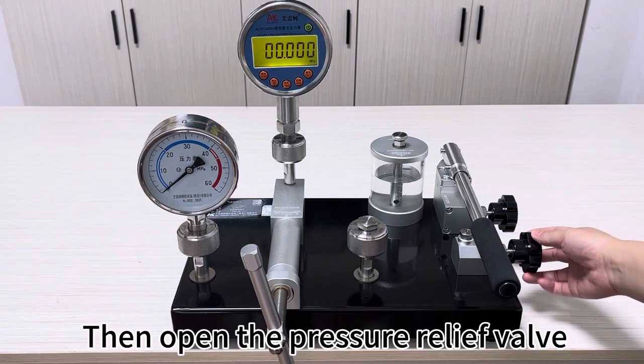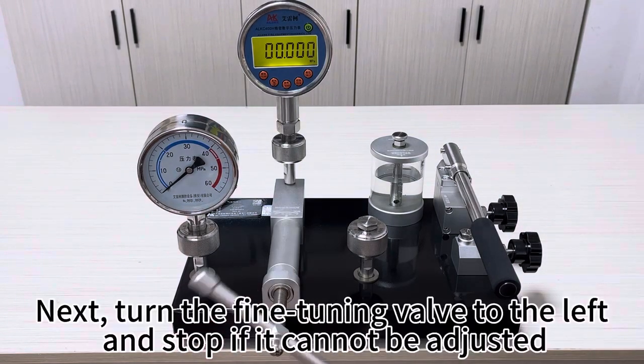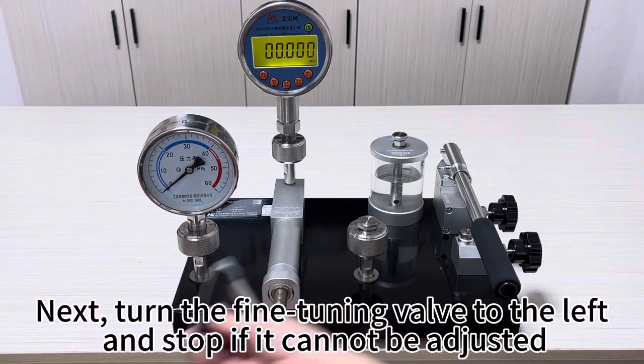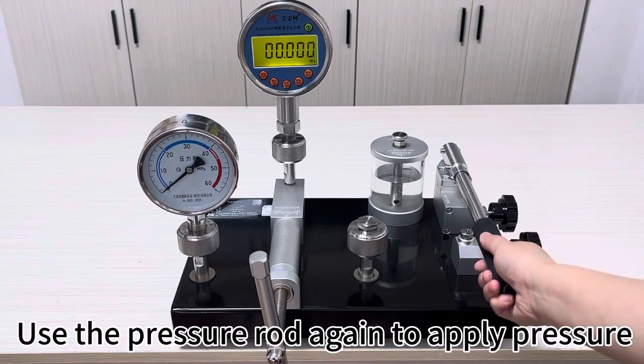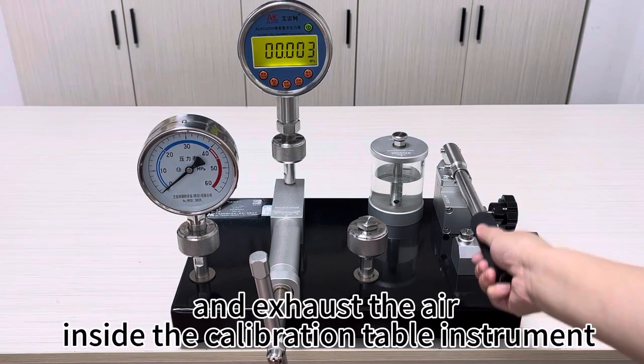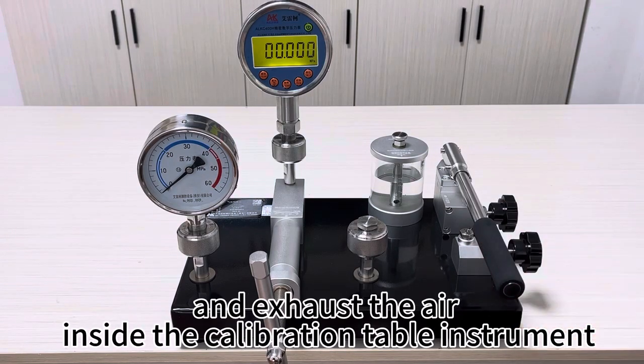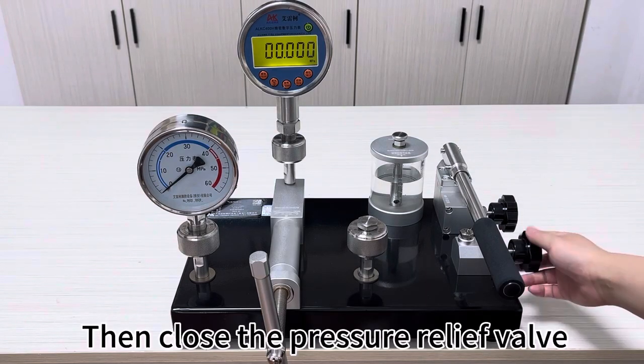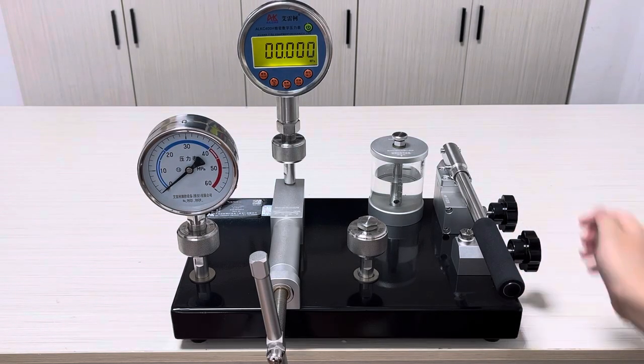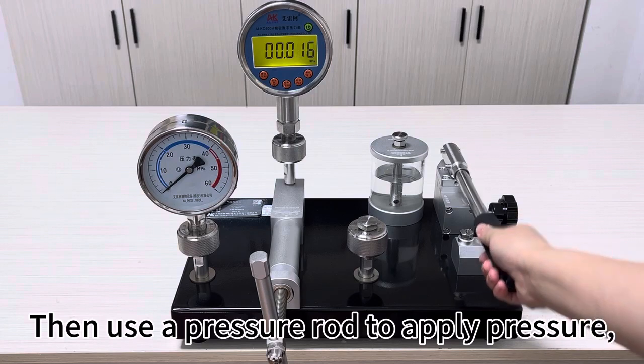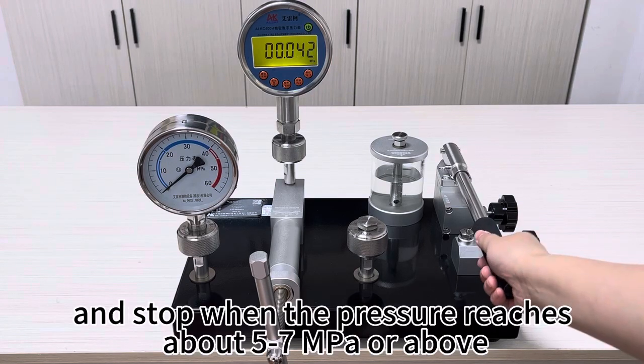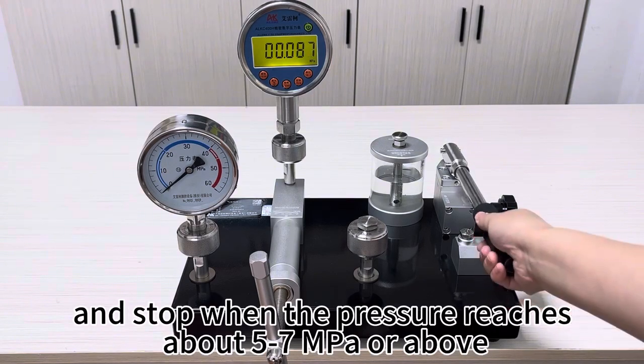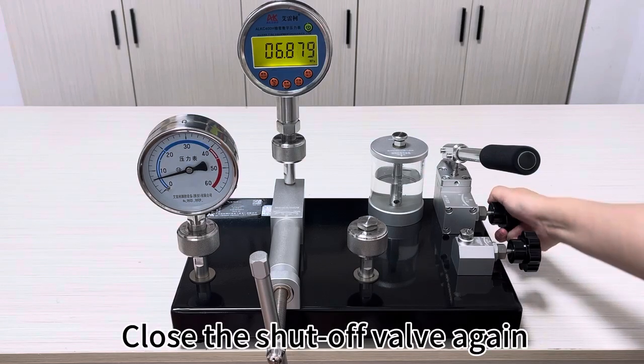Then open the pressure relief valve. Next, turn the fine-tuning valve to the left and stop if it cannot be adjusted. Use the pressure rod to apply pressure and exhaust the air inside the calibration table instrument. Then close the pressure relief valve. Then use the pressure rod to apply pressure, and stop when the pressure reaches about 5 to 7 MPa or above. Close the shut-off valve.